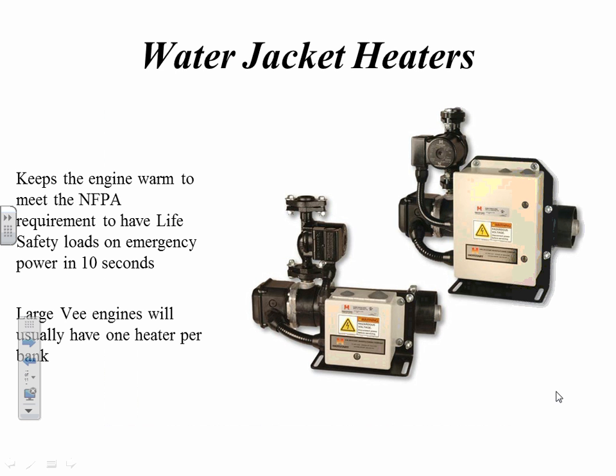Water jacket heaters. So I mentioned earlier, all these things have to start in 10 seconds. And that comes out of the NFPA 110. And what that means is the generator set not only has to start, but it's got to transfer over and be on emergency in 10 seconds. So it's imperative that they're kept warm, and they're kept warm all the time, even in the summer months.